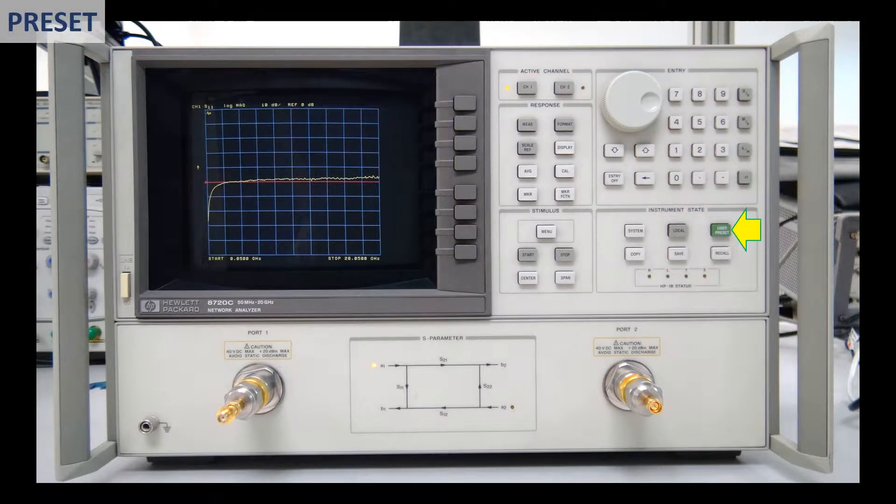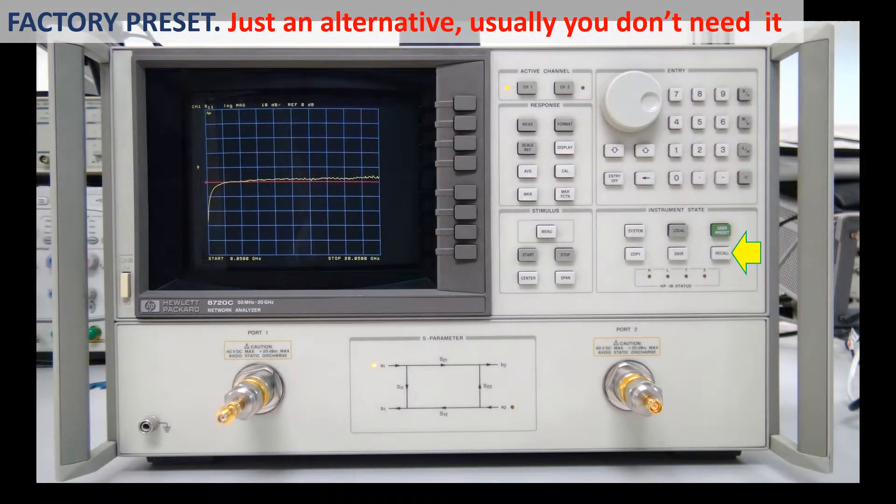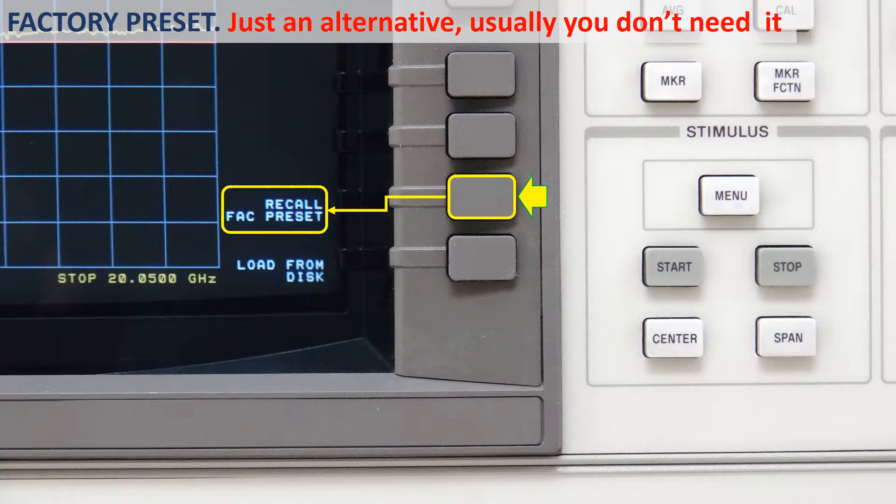I will start by pressing this green key labeled User Preset. It allows you to return the analyzer to a known condition. This condition is defined in a set of variables stored in one of the registries reserved to recover the instrument state. It is registry number 5. It is a registry that can be modified by the user. If you have problems recovering a known instrument state, you can also press Recall key and then the soft key named Recall Factory Preset to return to the factory default condition.